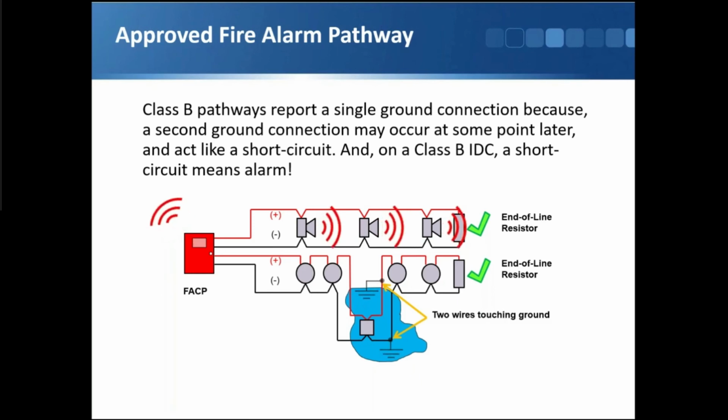And keep in mind that these wires I'm showing on this bottom here, as well as the top, could be the same pair of wires, albeit with wire nuts and whatever, but the same pair of wires was literally touching many, many points and had many junctions where a wire nut could come off and touch ground. So it was very important and very likely that these two legs could someday be shorted.